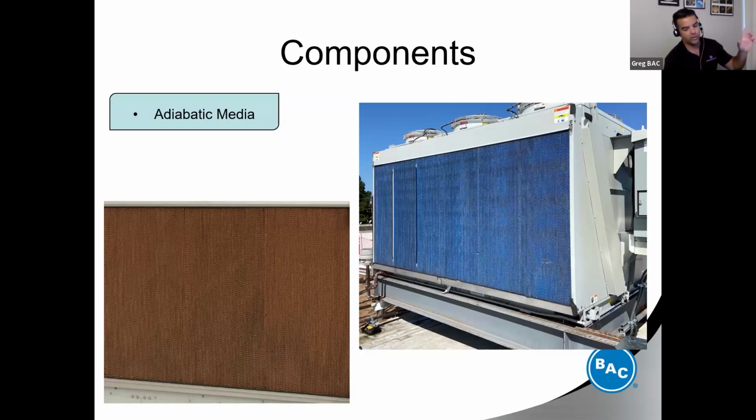You take one side out first. You clean them with your power washer or your hose. What you do is you let one pad dry in the sun, and if they're not too heavy, you can actually install them when they're still wet, because the unit will help you dry them off. But do not install all of them while wet, because they're not going to fit, since they have expanded. They're still a little bit too wide, and that will help accelerate the process.